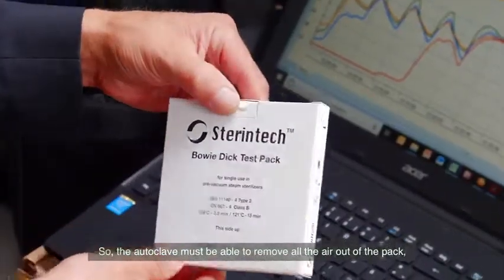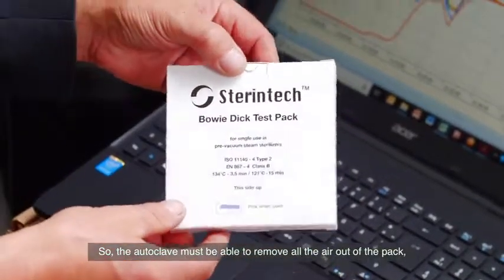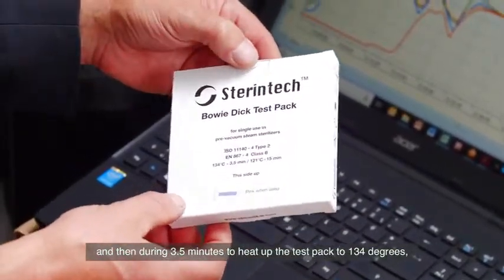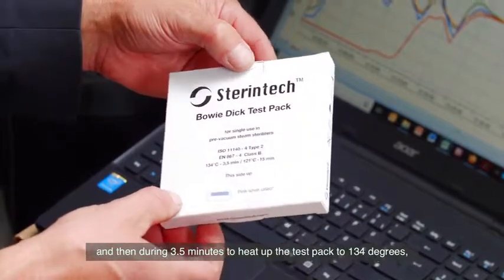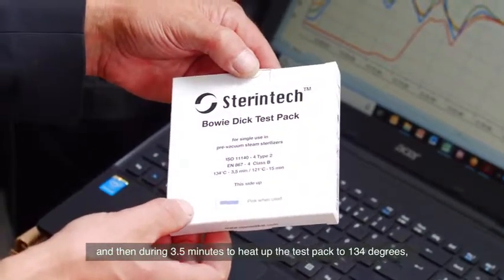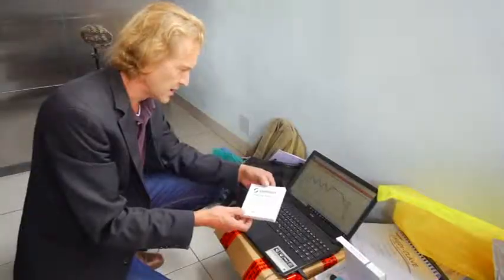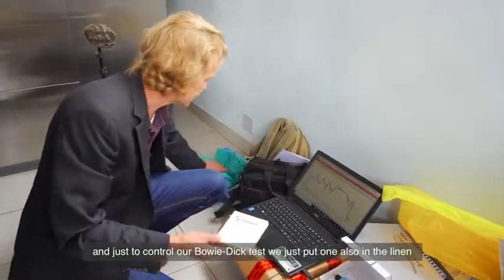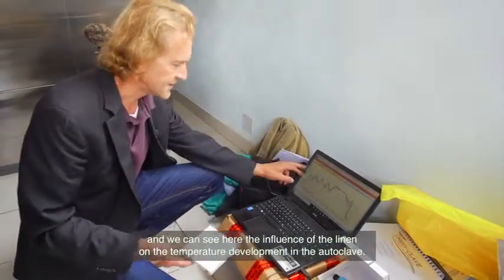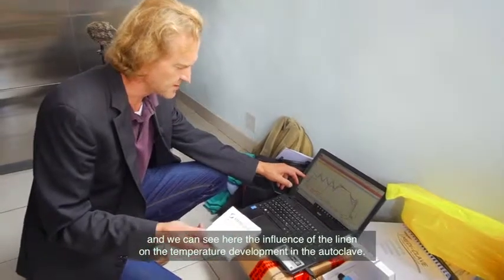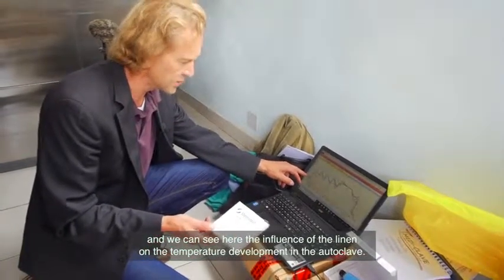The autoclave must be able to remove all the air out of the pack and then during 3.5 minutes heat up the test pack to 134 degrees. And just to control our Bowie-Dick test, we put the same also in the linen. And we can see here nicely the influence of the linen on the temperature development in the autoclave.